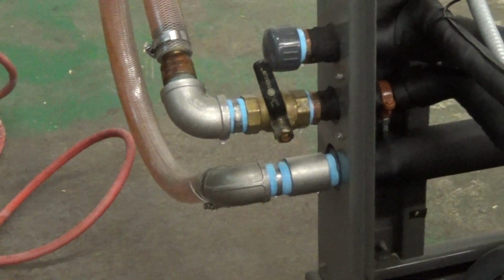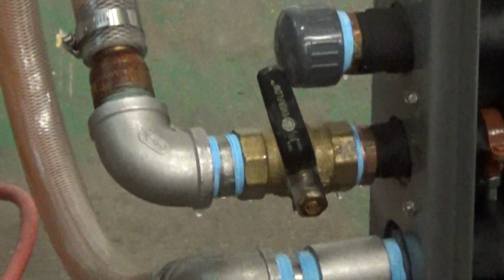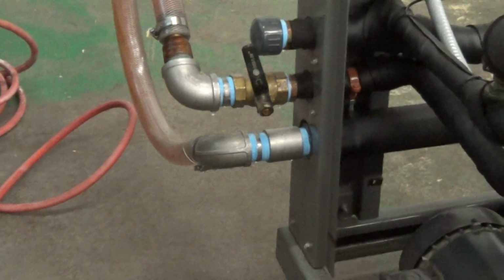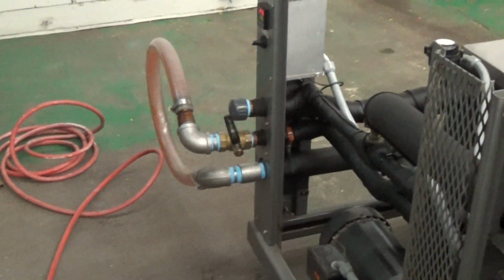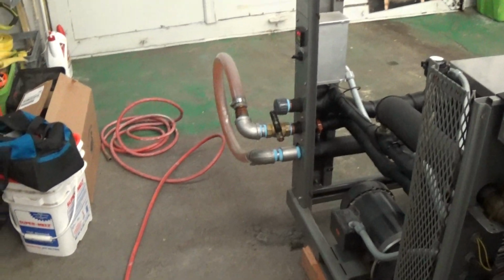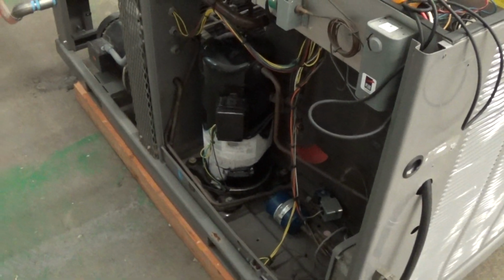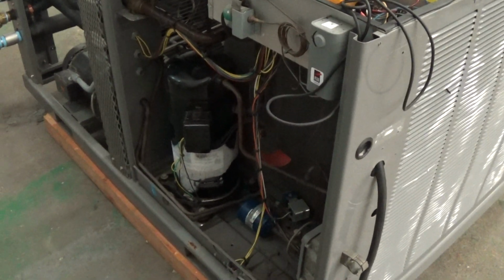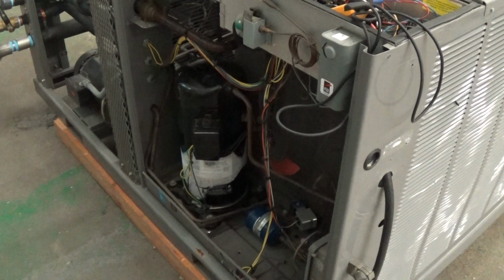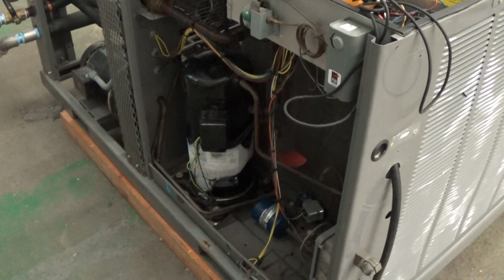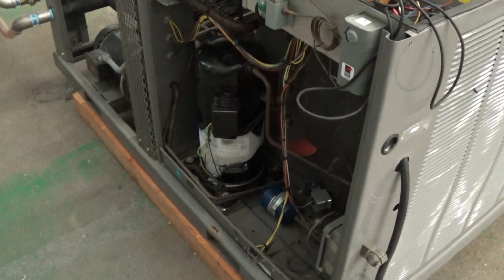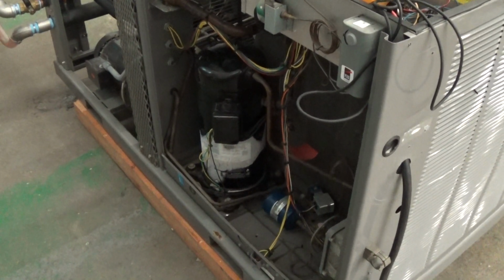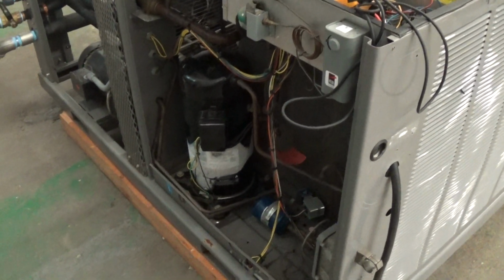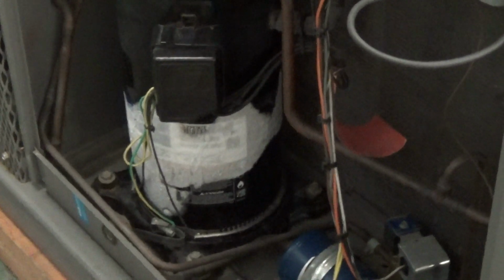If we had a little bit more moisture in the building, you would see ice build up quite a bit on those fittings. But because the dew point doesn't have enough moisture in it, you're not going to see that. You do, however, which is normal, contrary to what somebody who's only worked on air conditioning will tell you, when you're running at 28, 25 degree glycol temps, that R410A refrigerant is running a good 10 to 20 degrees colder than that. And that's what's going through the compressor and the lines and the heat exchanger and so forth. So building up some ice on the compressor, especially after running for 2 or 3 days, or a little bit of frost, is not uncommon at all.